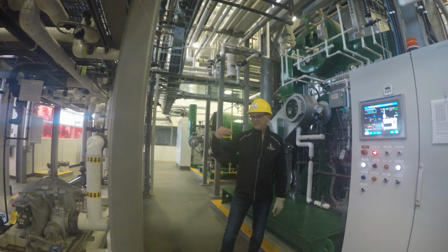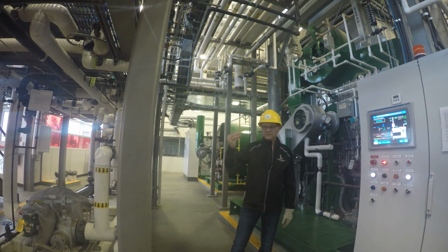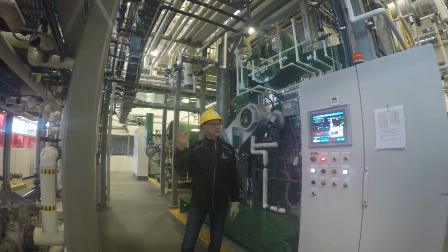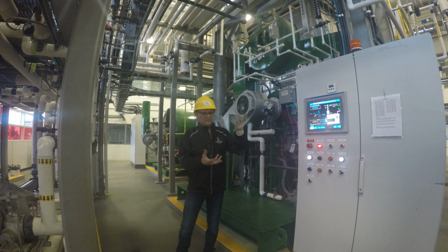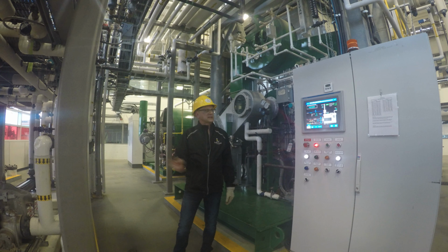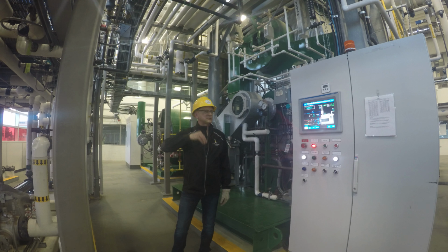And the other chemical we inject is an amine, which is a condensate treatment. The chemical actually is carried with the steam. Steam is the most pure form of water you're going to get. Nothing goes out with the steam. So as you're continually pouring water in and steam out, the total dissolved solids, the crap that builds up in that water, you've got to continually blow that out. And the amine is the only chemical that actually gets carried with the steam.